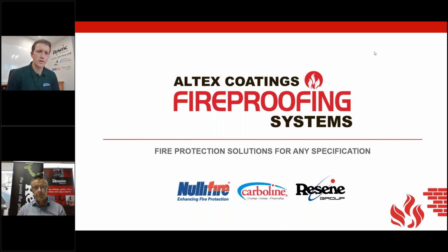Going back to the original question, yes, you can test for this. There are some pretty simple analytical techniques that you can use that we have access to here at Altex in Tauranga in our fire labs. It's as simple as taking a small sample of your fireproofing material, probably even as low as a 1 inch square is enough to give us an idea. Back down to the undercoat, we can take that particular sample and run it through FTIR, which is an infrared spectroscopy analytical technique.